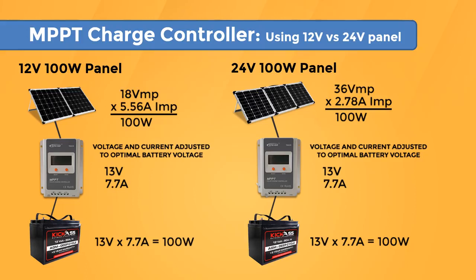This is very useful, as higher voltage panels are usually also higher wattage. So you can get a panel that is 200 to 300 watts in a 20 or 24-volt nominal panel, whereas 12-volt panels tend to go well under 200 watts. The higher wattage panels are also generally less expensive per watt than the smaller panels. So depending on your system, they can often be the less expensive solution to go with, compared to the bigger panels and the MPPT charge controller, even though the charge controller is more expensive.